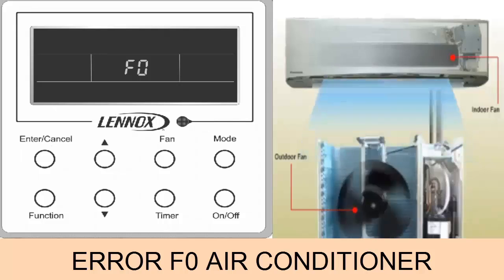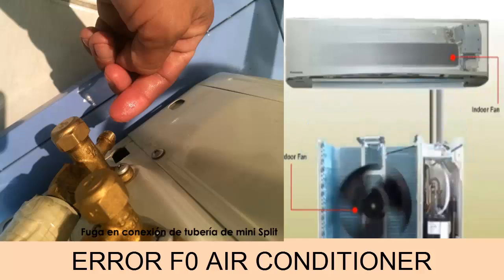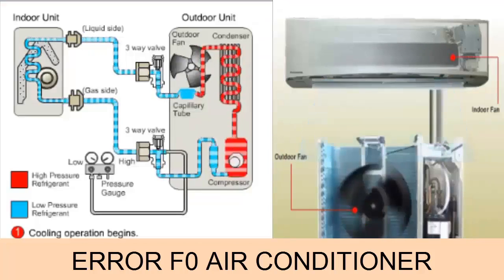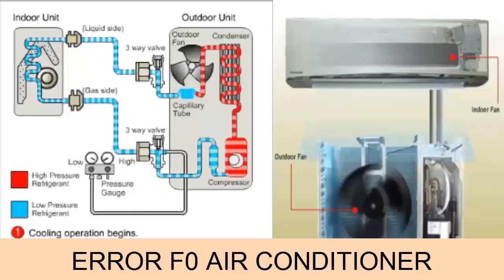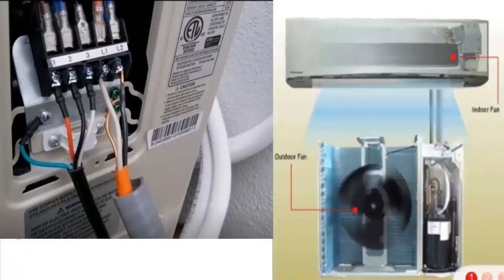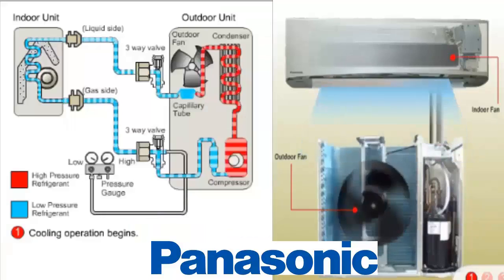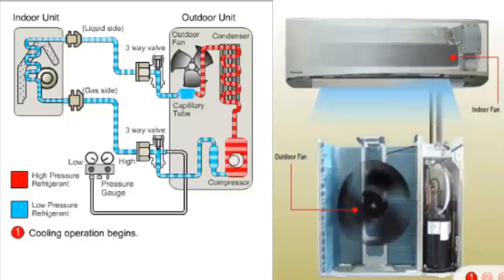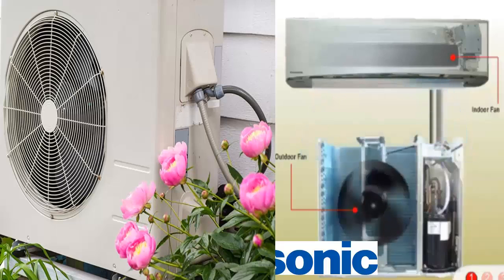In summary, error code F-Zero, depending on its meaning, can be attributed to various causes, such as: refrigerant leakage, which can affect system pressure and cause it to enter protection mode; issues with the ambient temperature sensor or coil temperature sensor; overcurrent in the system triggering error F-Zero due to protective mechanisms; and abnormal condenser fan speed, which can affect the cooling process and lead to errors.